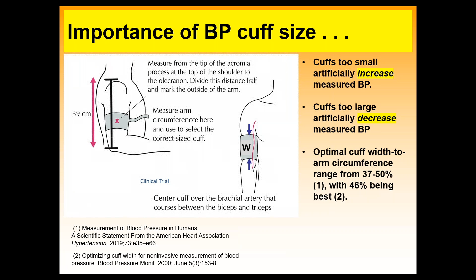And the converse is also true. If you've got a small person, a frail elderly person, with a standard adult cuff, now that ratio is going to be too large, and you're going to get artificially lower than normal blood pressures. And they might say, well, I've always had low blood pressure. Well, they indeed may have had low blood pressure, but it could also be artificially reduced by the inappropriate cuff size. The general recommendations for the ratio are about 0.4, 37, 40-some percent. So the width of the cuff, and it's the bladder, not the full width of the blood pressure cuff itself with the case on it, the bladder width divided by the circumference of the arm. If that's around 0.4-ish to 0.5, you're generally in good shape.